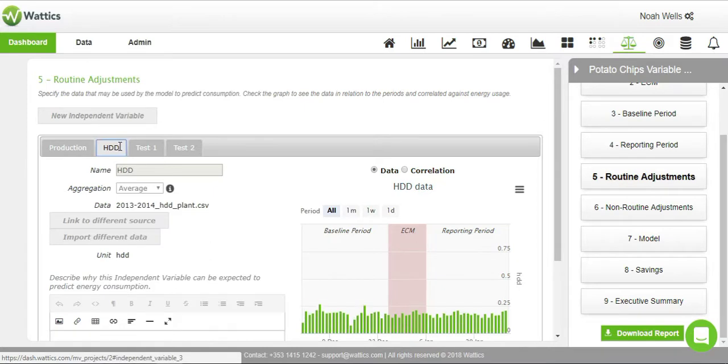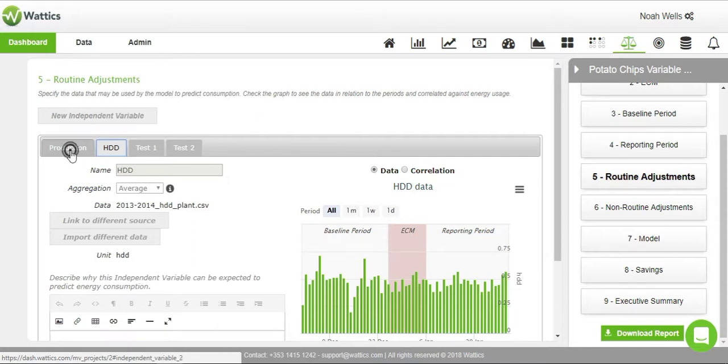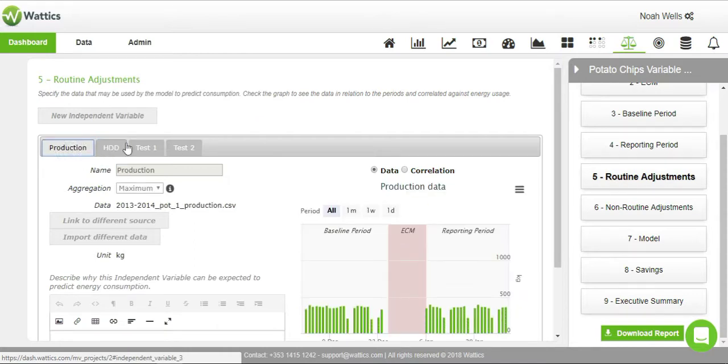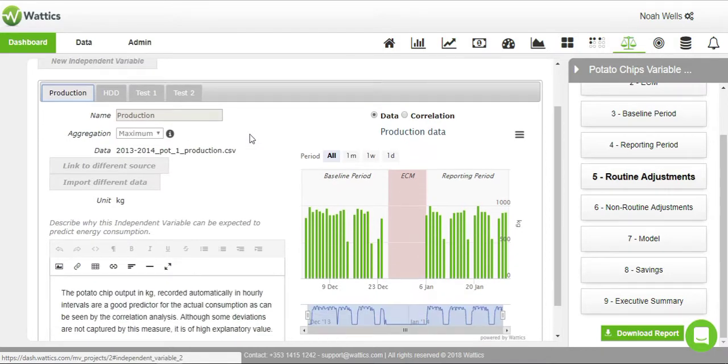The routine adjustment section allows you to import any measurements for factors that routinely vary and significantly affect energy use, such as operations and weather conditions. In this case, two key independent variables were imported. Variables such as production or the kilograms of potato chips processed can be uploaded by linking to a different source. Otherwise, you can upload the data via CSV file again.